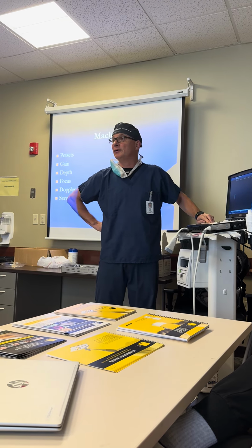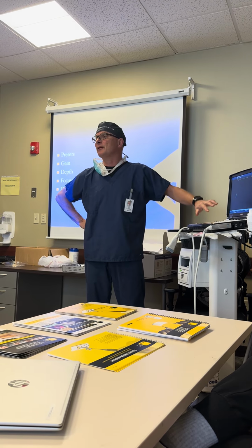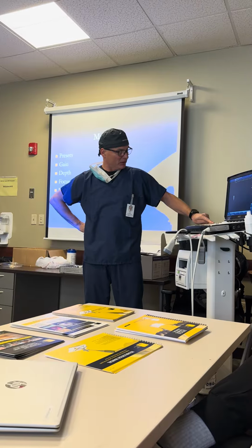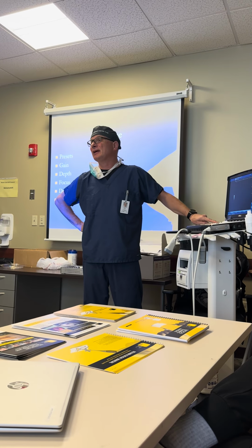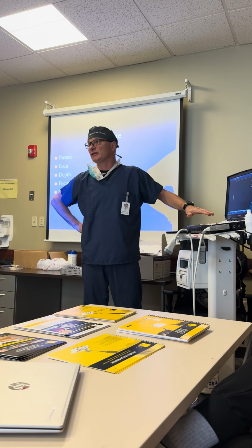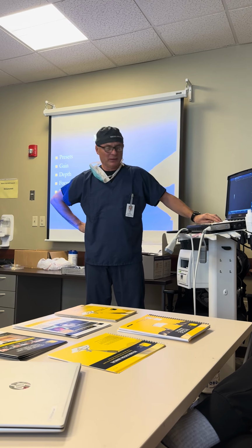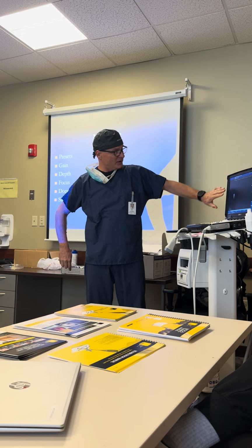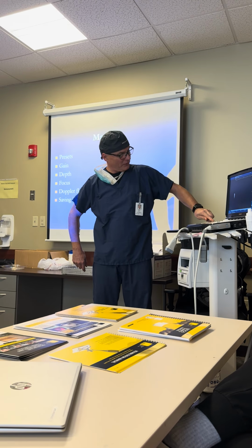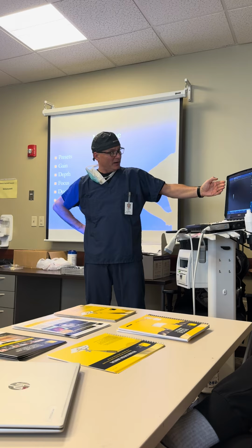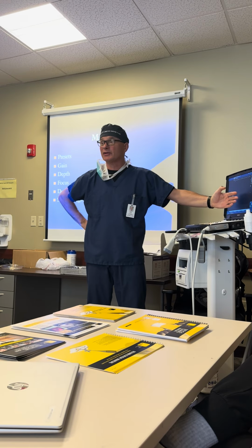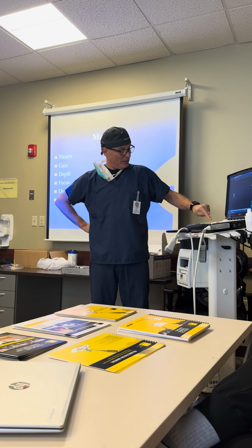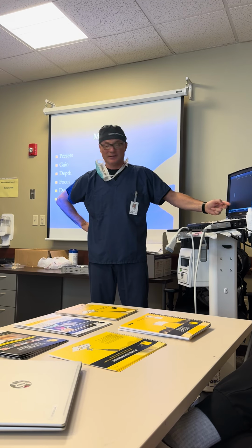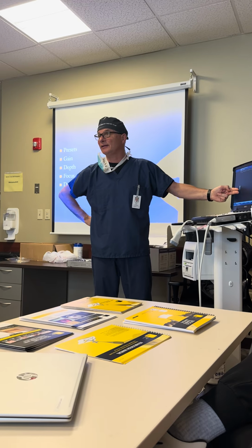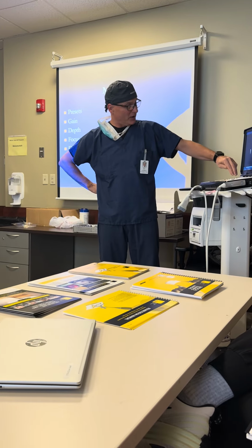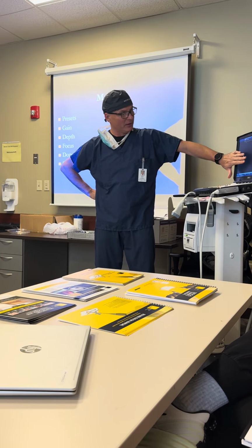The other knobs that very, very frequently get messed up when we are cleaning the machine are these small toggle switches here. They call them time gain compensation (TGC) channels or TGC switches. What you can do with these toggle switches here, imagine that every 1, 2, 3, 4, 5, 6 we have on this machine. So basically you have 6 horizontal bands on the screen, right? The bottom one controls the bottom sixth. The one above controls the fifth part of this. So each and every one of these controls only one segment of the screen.